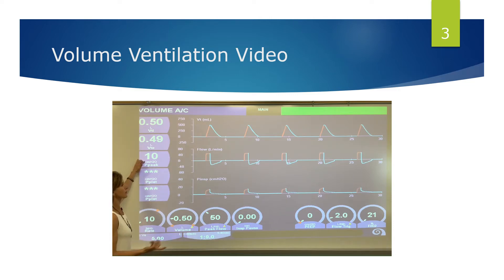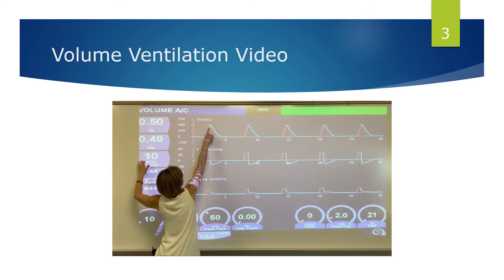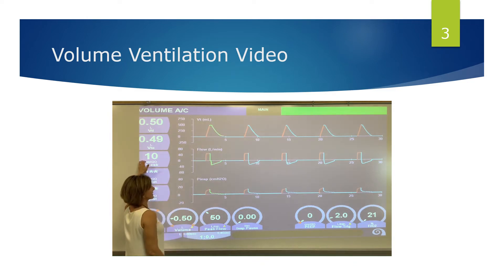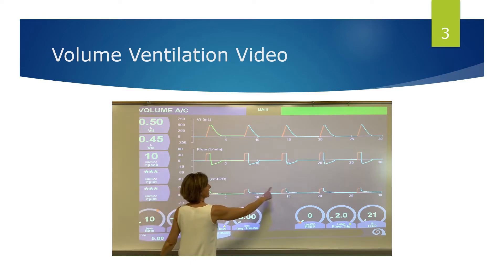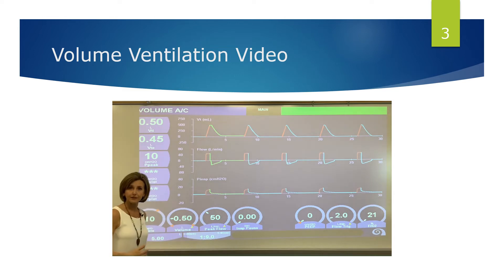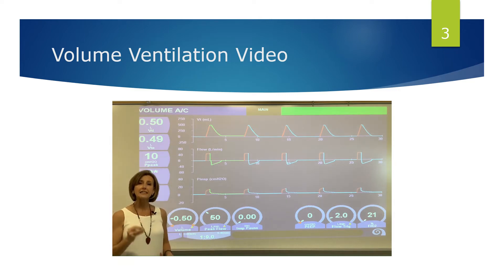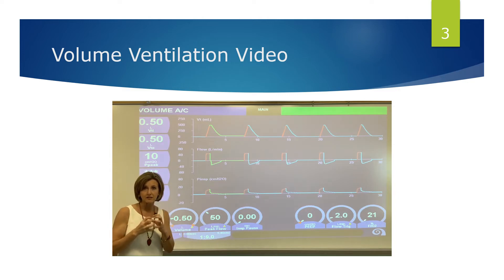Looking at our graphics display: we're pushing 500 mL in, it's coming out on exhalation, and it's taking a peak inspiratory pressure of about 10 centimeters of water for that volume to be pushed in. Now I'm going to change the compliance of the lung — I'm going to decrease lung compliance, making the lungs stiffer.